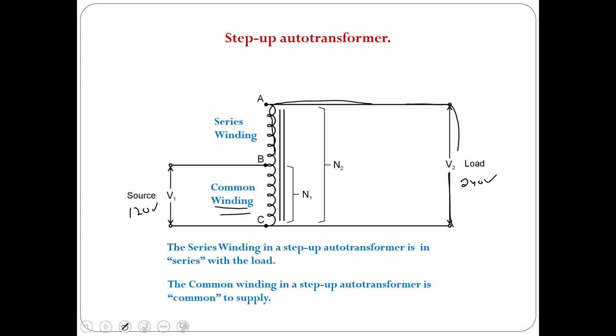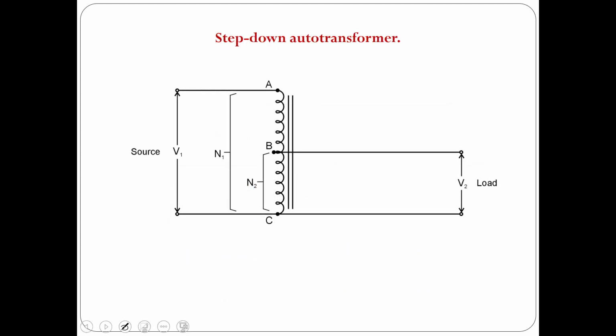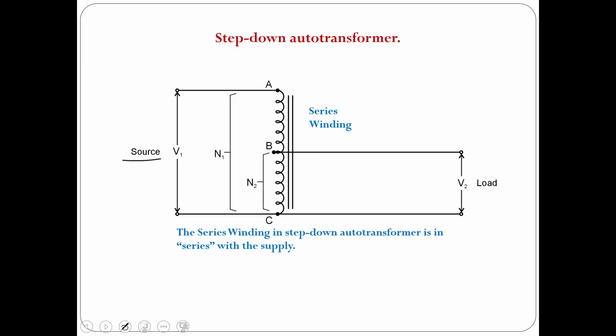Okay. If we look at a step-down autotransformer, we have both the series and common winding, but this time in a step-down, the series winding is in series with the supply or the source, and the common winding is going to be common to the load. So whatever voltage is on the common winding is going to be the same as the load voltage.